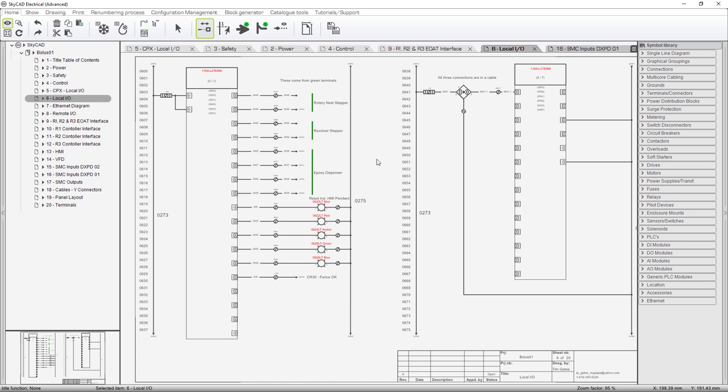Epoxy dispenser. This is the discrete wiring that goes from our controller out to the epoxy dispenser to control it. We also added a stack light up on top of the main panel. That first light though is not a stack light. That's the blue indicator that is in the reset push button that's mounted on the HMI pendant. And then we have red, amber, green, and blue. Those are the four lights in the stack light. And then we have a signal from the PLC to the CR30, the safety circuit, saying that the fence is okay.